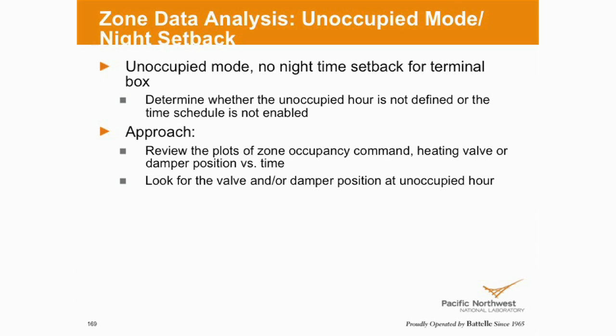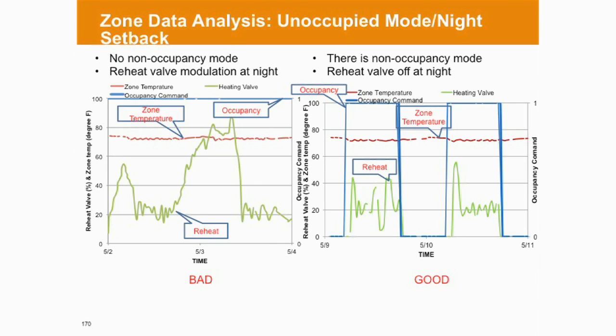So if there's valve modulation or damper modulation during unoccupied hours, that's a good indicator. So here is one of the charts showing the zone before retuning and after retuning. On the left side chart, you can see that the zone temperature is maintained well, about 72 to 74 degrees, and during unoccupied hours, at nighttime, you can see that the reheat valves are still open during nighttime.